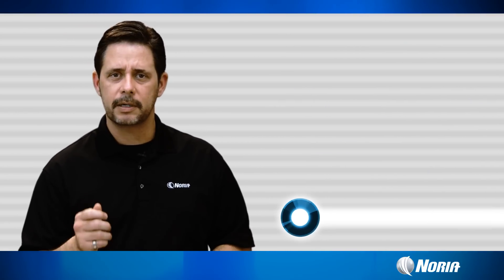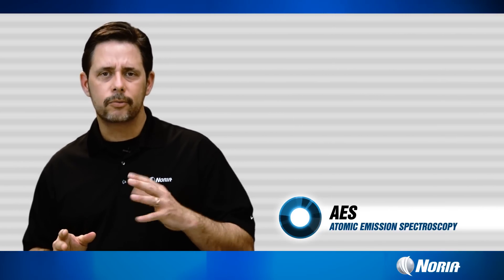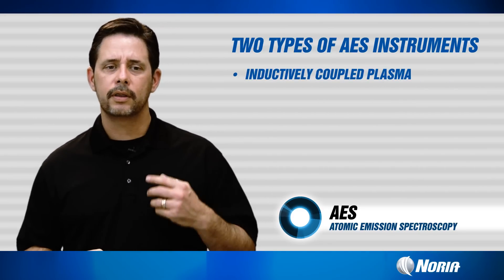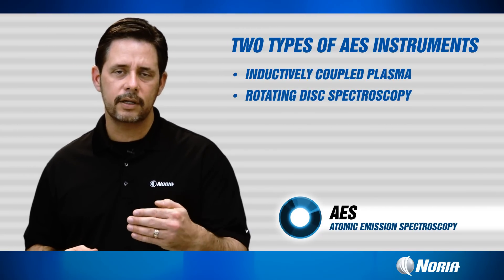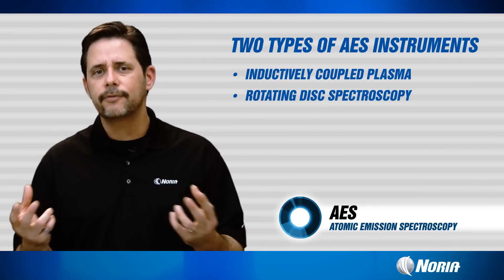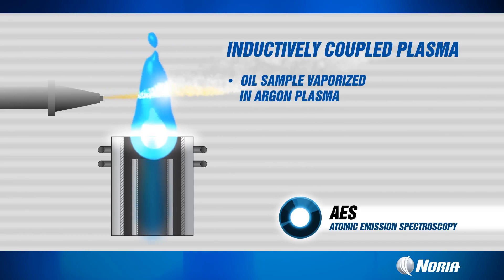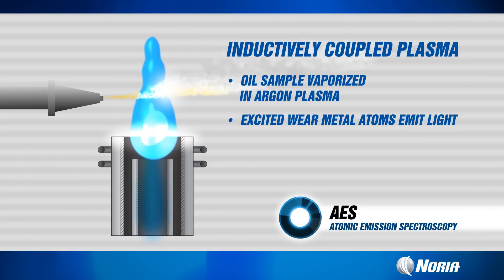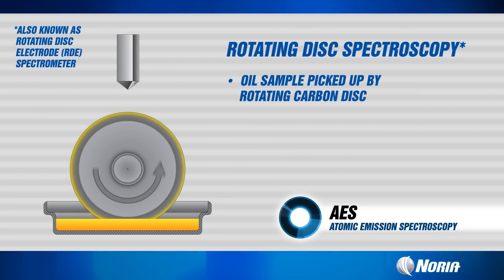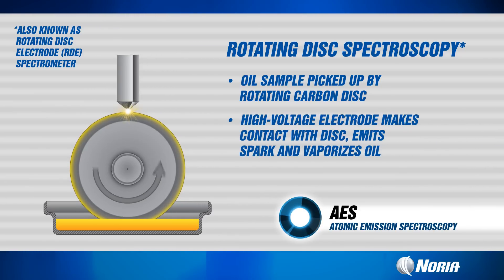Our used oil analysis labs today for the most part use one of two types of instruments: either the ICP or the ROTRODE. The ICP stands for inductively coupled plasma. ROTRODE is rotating disc spectroscopy, or arc spark emissions. The main difference between these two methods is really just how the oil sample is vaporized. The ICP sample is vaporized in an argon plasma, exciting the particles which then result in light emission. With rotating disc or ROTRODE spectroscopy, that sample is picked up on a carbon disc and passes underneath an electrode where a high voltage spark contacts the oil, vaporizing it and exciting the particles, causing them to emit light.